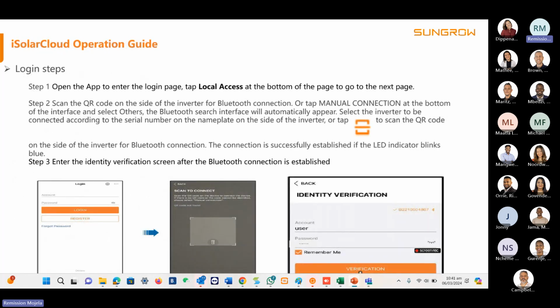And then basically to log in, you just have to scan the QR code of the inverter or scan the QR code of the communication module, which will be the Logger 1000 or the IM4. But with the IM4 and the Logger 1000, you can't use the app to commission. You can only use this method to connect directly to the inverter when you're locally on site, or use this method with the WiNet-S.